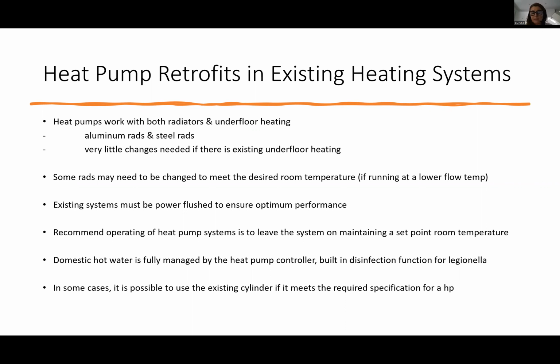There is a requirement under the SEAI grant funding that a heat loss calculation needs to be carried out to make sure that the existing radiator will still be able to heat that room if you use a lower flow temperature from the heat pump. So ordinarily you might be heating that radiator at 60 degrees. Now you want to run your heat pump at 45 degrees. Will the existing radiator be big enough, or will it need to be replaced with a larger radiator in order to meet the desired room temperature?